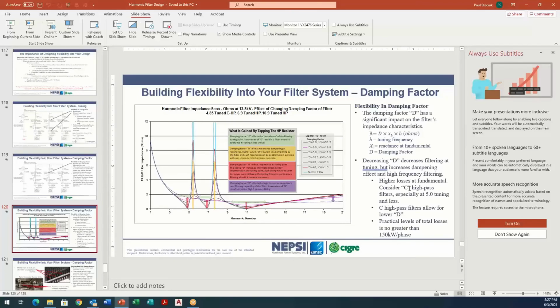If you're dealing with an industrial facility, knowing the total harmonic current of the system that's available for the filter would be the starting point, and then designing filters that would be able to absorb 100% of that current would be a conservative way of approaching it.